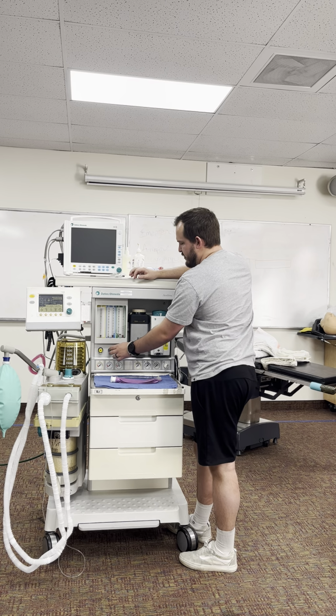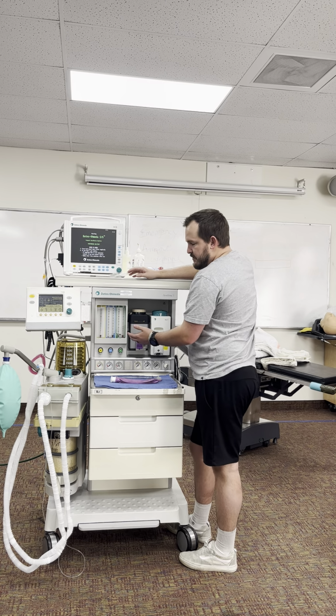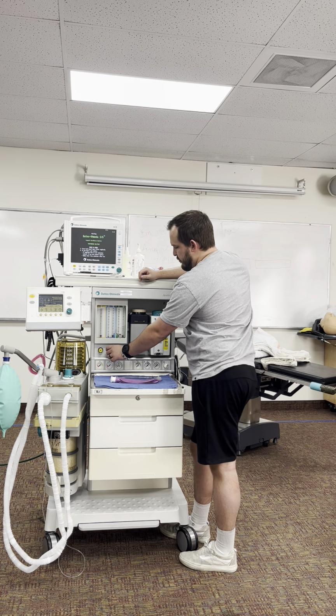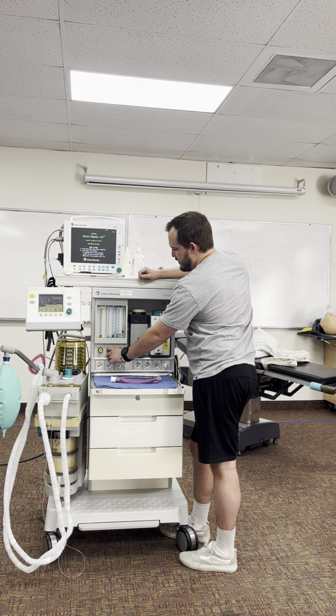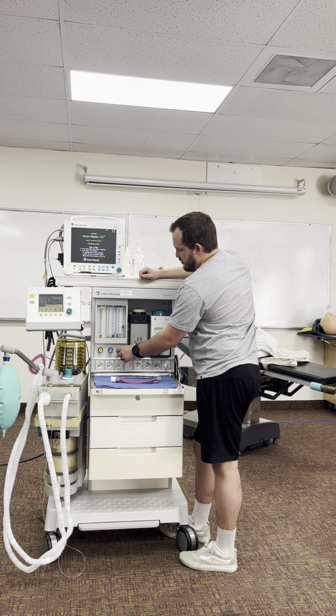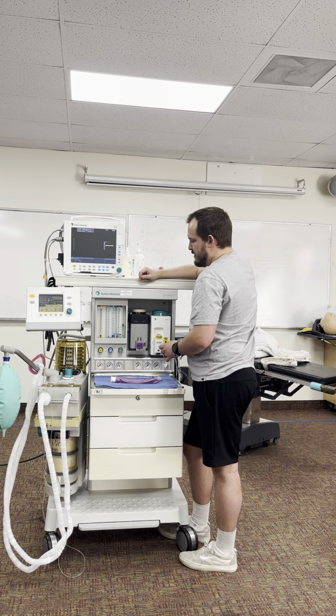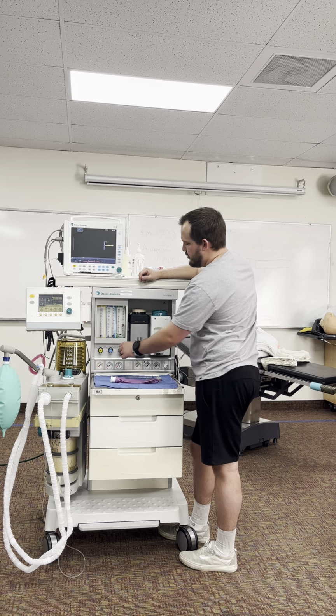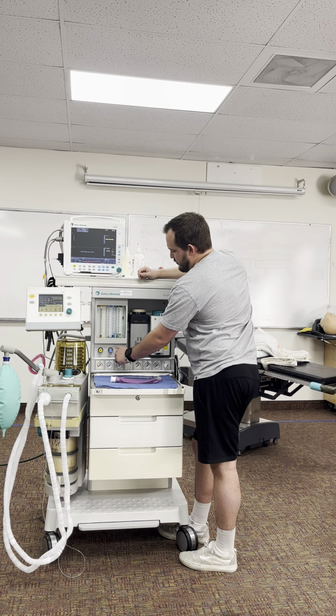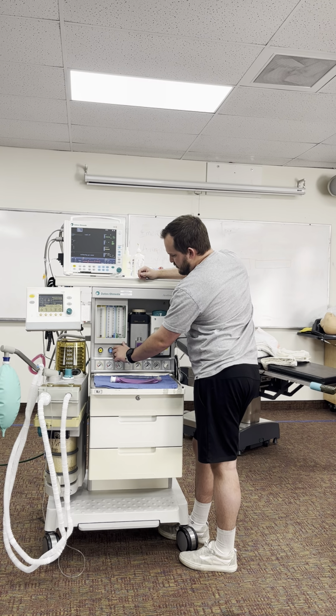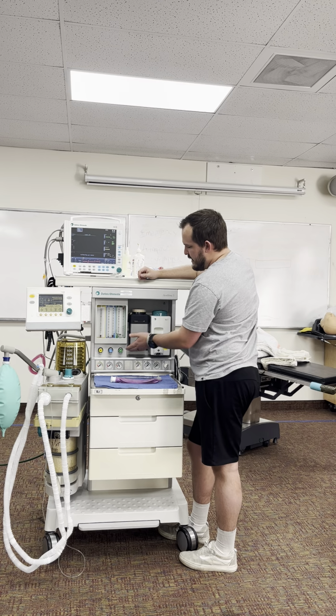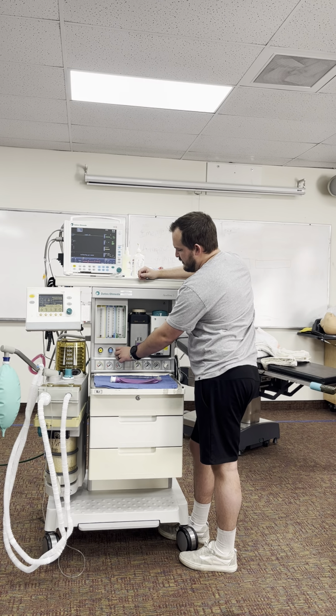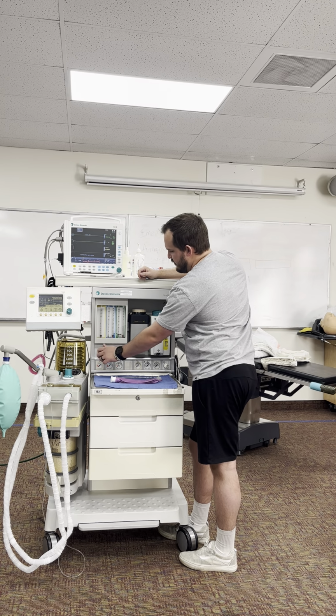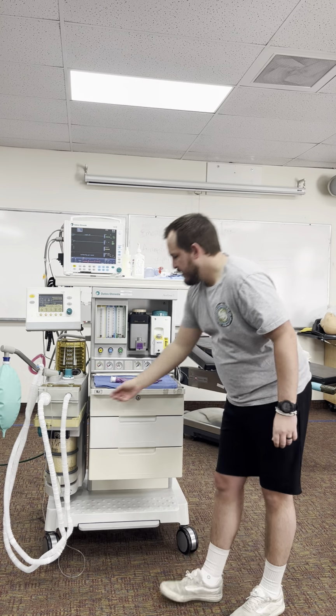So now for nitrous, I'm going to do the same thing, but I'm also going to double check that it can't make a hypoxic concentration. So as I increase my nitrous, my oxygen should also go up, which it does, and that should maintain a 3 nitrous to 1 oxygen ratio on the liters per minute. So then I'm going to increase my oxygen all the way, make sure there's no problems. There isn't any. And now going down, as I decrease my oxygen, the nitrous will also go down to make sure it doesn't create a hypoxic concentration, which is what happens. So we're good there.